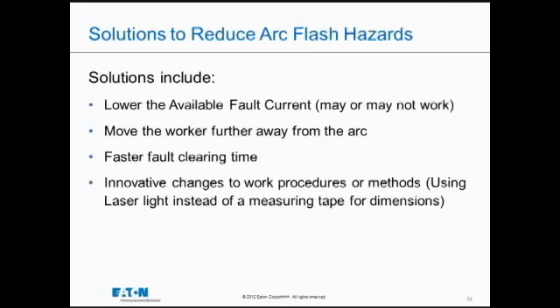And the problem with that approach is that it is difficult to reduce short circuit current. You'd have to introduce some impedance in the circuit, so higher impedance transformers, longer cable runs, or higher impedance in your circuitry. Either transformers or cables is where you introduce that. And even if you did introduce a lower current, what you're going to get as a problem is not faster operating speed for your protection, but slower. So you introduce a less powerful arc, but it takes longer to get rid of it. And that's generally what happens with that solution. So it's generally bypassed. We don't use that one.